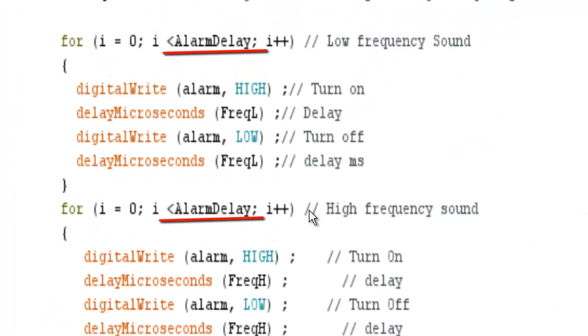The alarm delay value is created by taking your sample counts, dividing it by 5. So as that sample value gets closer and closer to 0, your alarm delay will get closer and closer to 0. So if you have, say, 1,000 divided by 5, we're going to start off with an alarm delay of 200. And as we get smaller and smaller of our counts that we've read, the alarm delay will get shorter and shorter, which will result in a faster and faster repetition rate between the high and the low frequency sounds.